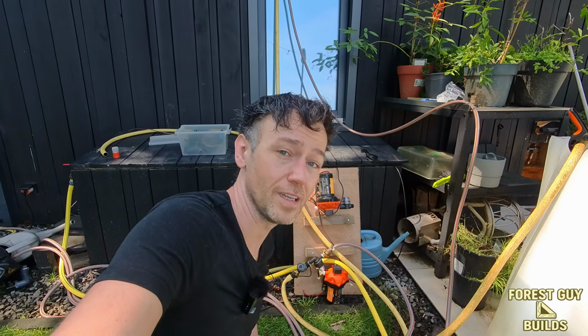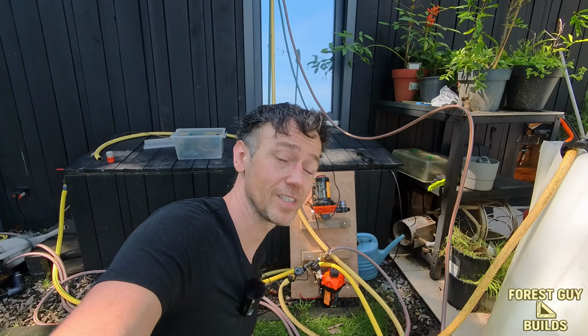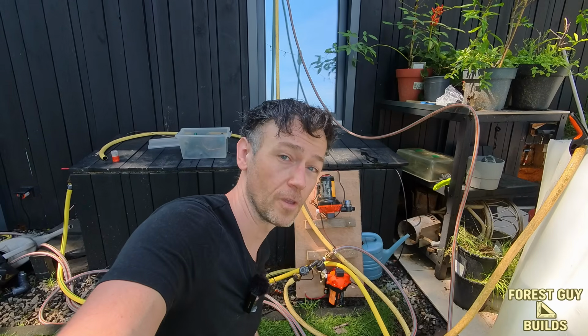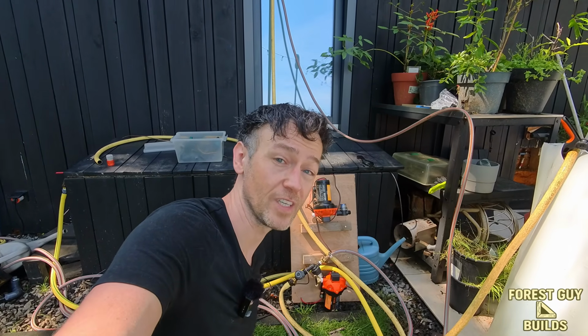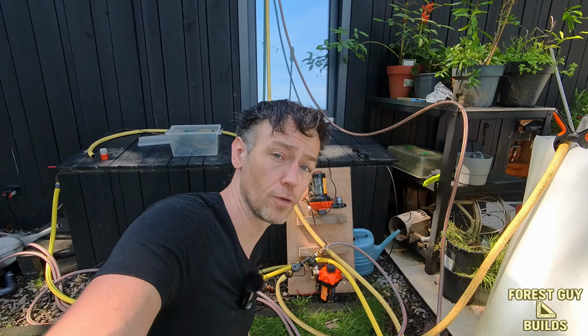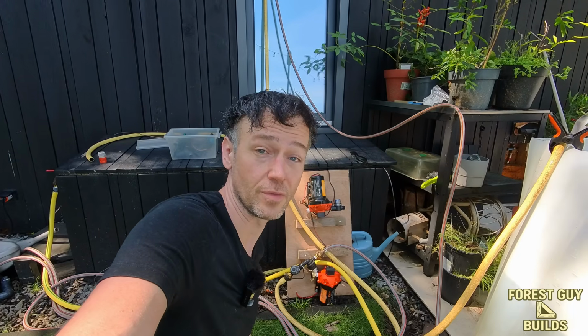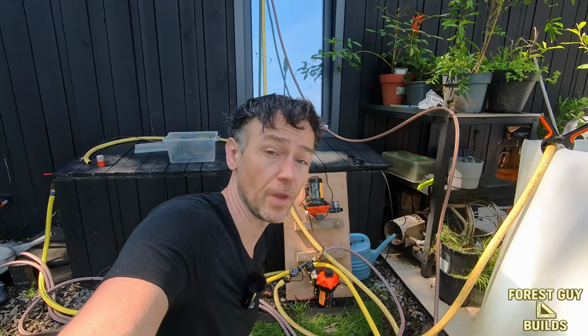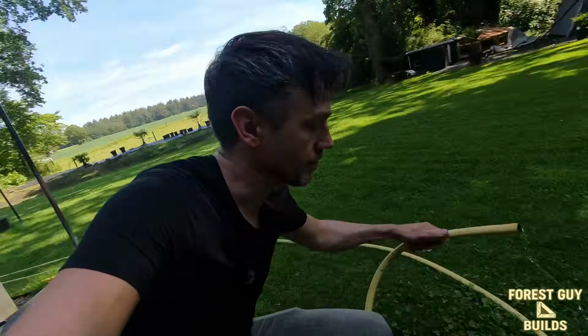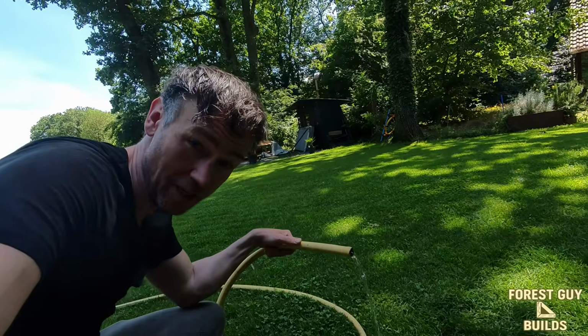By having a limited flow on the groundwater circuit, I'm able to impact the temperature that goes to the floor. If the flow on the groundwater side is too high, the temperature to the floor lowers to about 15 degrees, which causes condensation. With this lower flow, I'm able to have a temperature of about 17 degrees to the floor, which is much better. Of course, it's really hard to say exactly how much energy is being transferred.